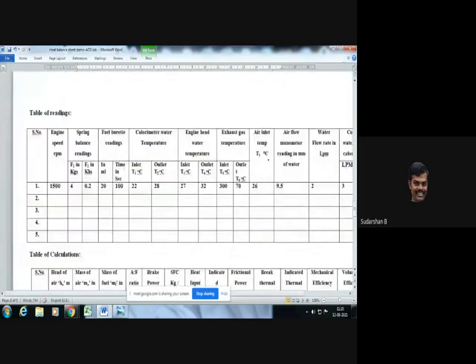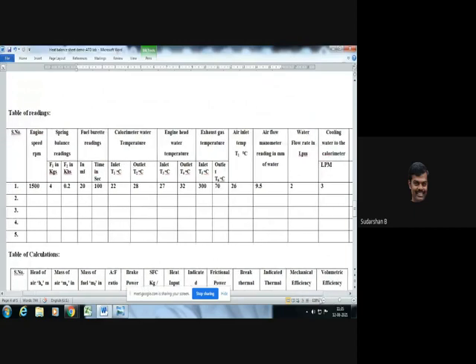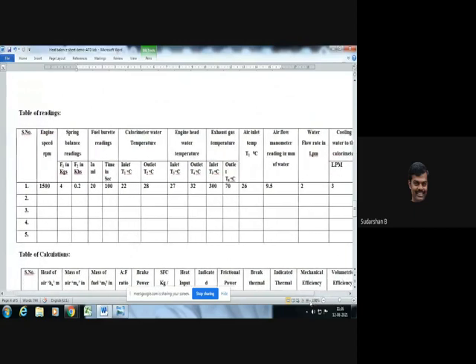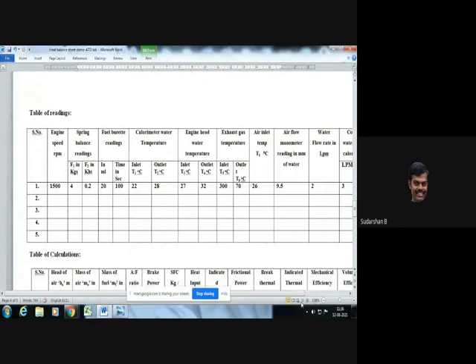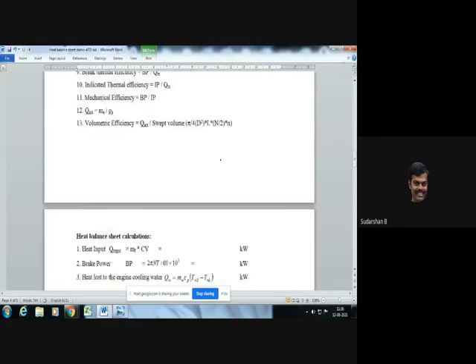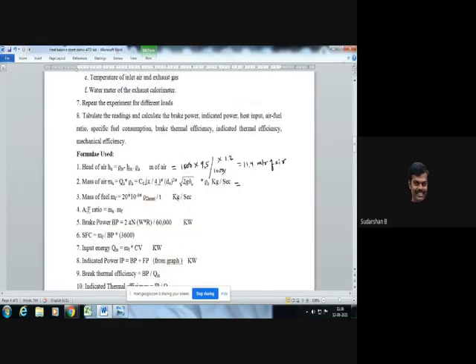This directly we have to put in terms of CD, pi by 4, D naught, all these values you have to put forth, for Q of air through the orifice using this standard formula. HA is 11.4, and density of air is considered 1.2 at normal temperature condition.